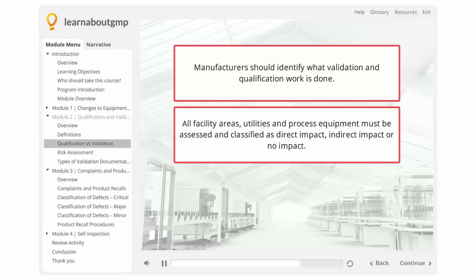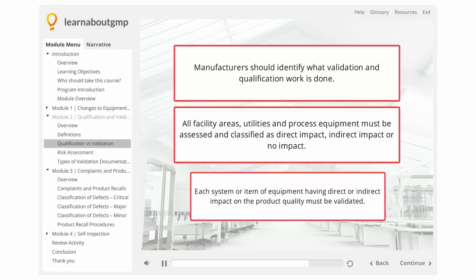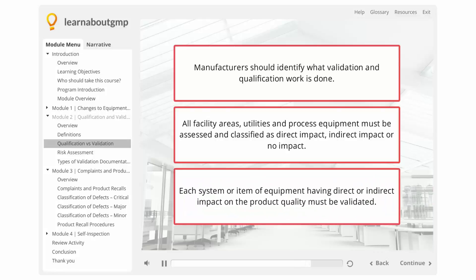This classification follows an analysis of their impact on the identity, strength, quality, purity, or safety of products manufactured at the facility, and also the safety of the operations and environment. Each system or item of equipment having direct or indirect impact on product quality must be validated. The extent of validation or qualification should be determined by performing a risk assessment of that particular system or equipment.